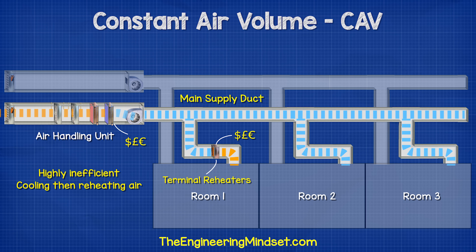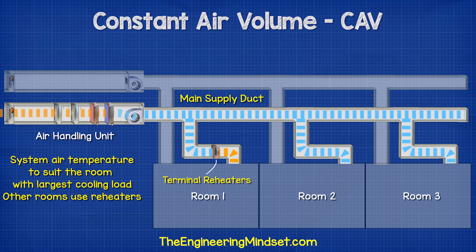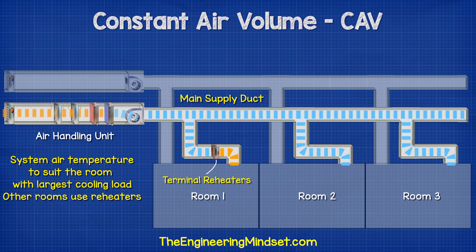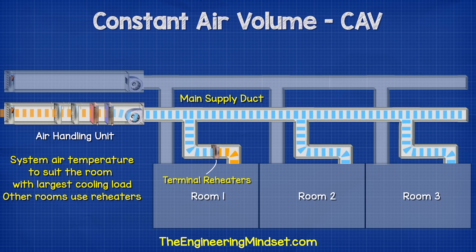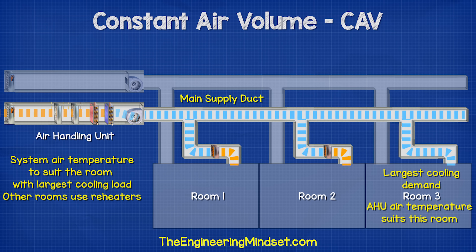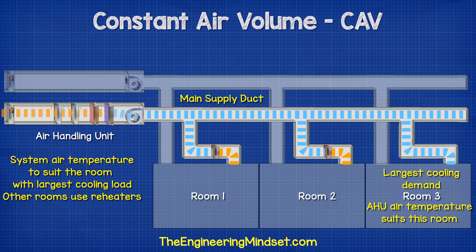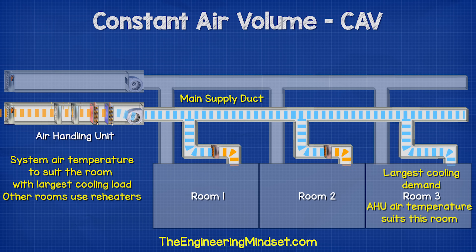Typically, the air temperature for this system is supplied at the coldest temperature possible which satisfies the room with the largest cooling load. For example, one room might have the largest cooling load so the system provides the air temperature to suit that particular room. The other rooms would then have to use reheaters because the air is going to be too cold.